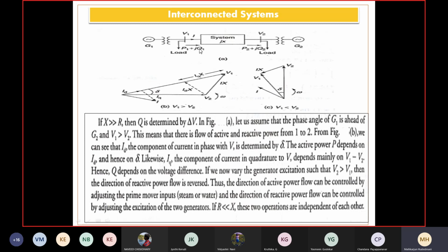It means power flow can occur in an interconnected system from bus 1 to bus 2 or bus 2 to bus 1, depending upon the leading and lagging of the voltage. So the delta of the system matters here. This delta is called the power angle. You can see this delta: delta is the angle between V1 and V2. So this defines how the power flow occurs. In an interconnected system, when power flow is noticed, excitation control from the generator perspective makes it possible to decide whether to deliver or whether to absorb.